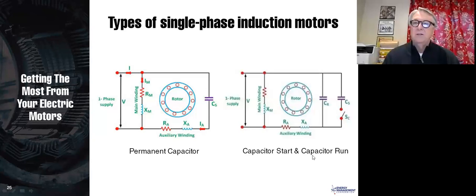Let's use a capacitor start and capacitor run. In this case, we'll use a large capacitor in order to give us a lot of starting torque. And then once it comes up to speed, we'll take that out of the circuit with a centrifugal switch or some sort of device. And then we'll leave a much smaller capacitor. And this is the most common motor out there. This gives you the most starting torque and also the highest efficiency and a good power factor when you're running. So that's a nice motor, but it's more expensive because you've got to have more parts in there.